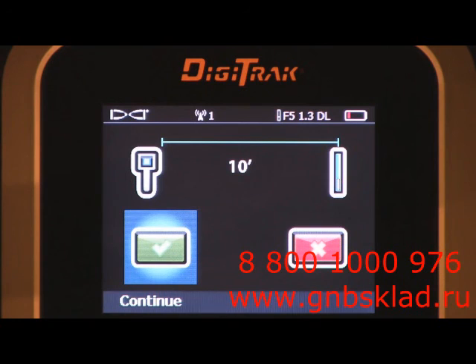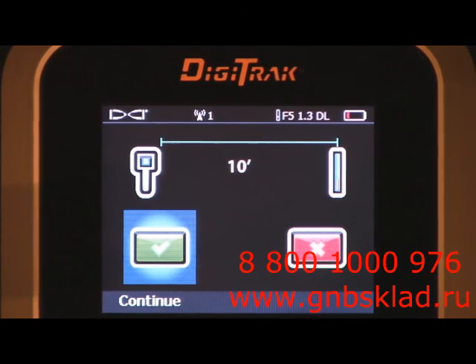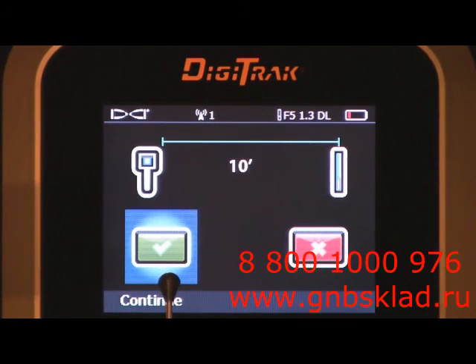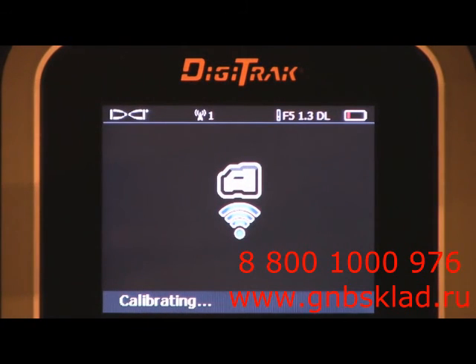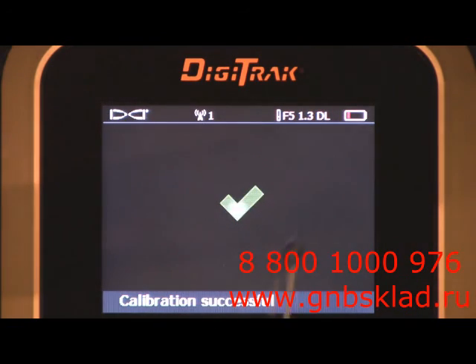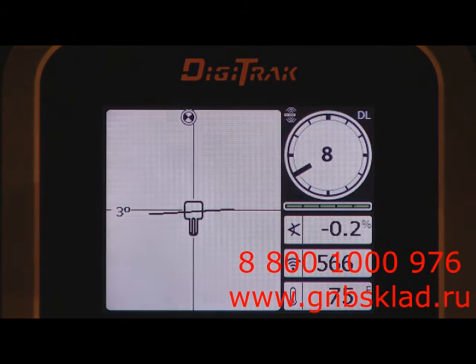Ideally, you go into a clean environment with the transmitter in the housing only, put it flat on the ground, keep it level, and go off to the side of it your prescribed distance. And then you begin your calibration sequence, which I'm going to do right now. Make sure the green check is highlighted and click it. We're now measuring signal strength. At the end of this measurement cycle, it'll flash and let you know your calibration is good. There we go, green check means it was a healthy calibration. And now we're back to the main screen.